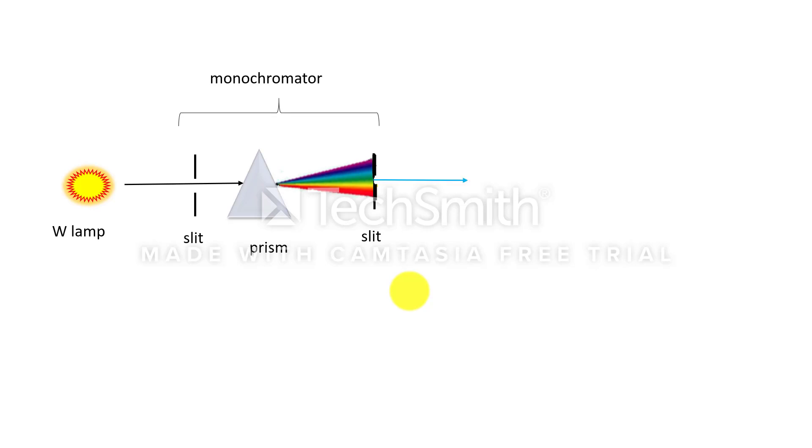The light of single wavelength is allowed to pass through the sample taken in the cuvette and the transmitted light is allowed to fall on the photocell where photoelectricity will be generated and it is allowed to pass through the recorder where it is displayed as absorbance.